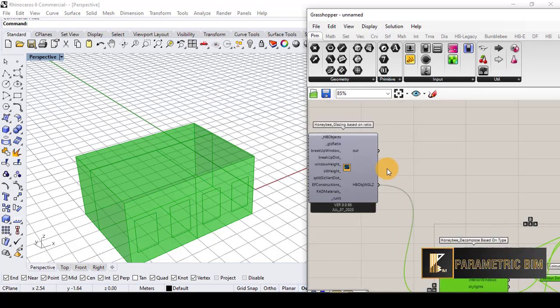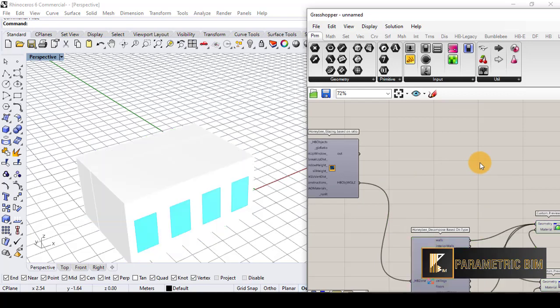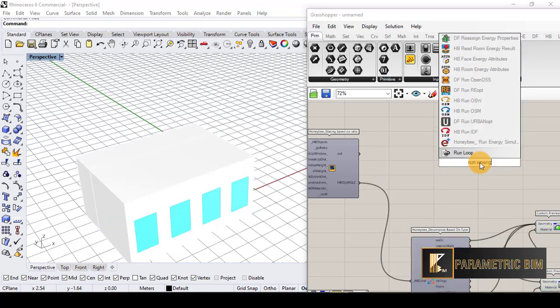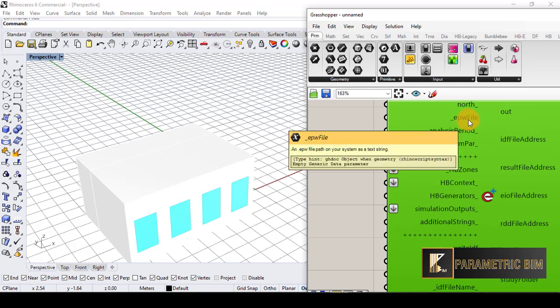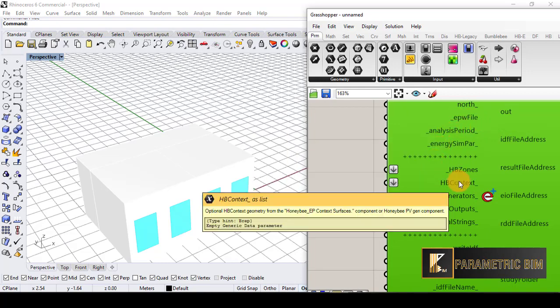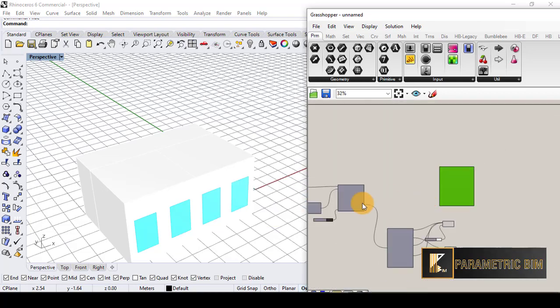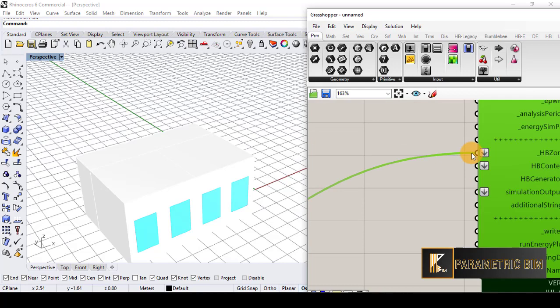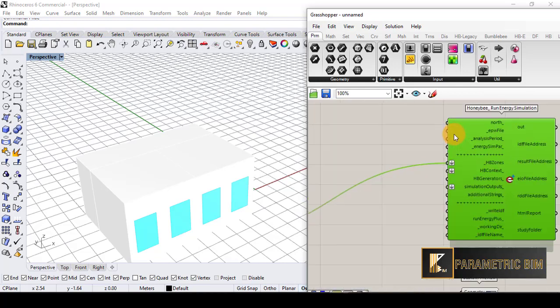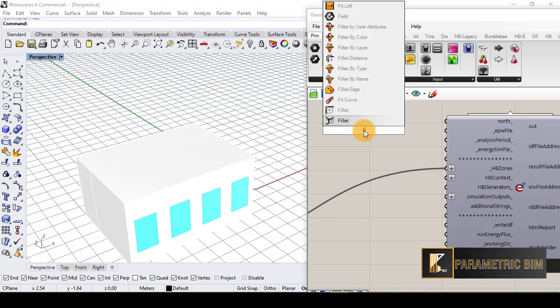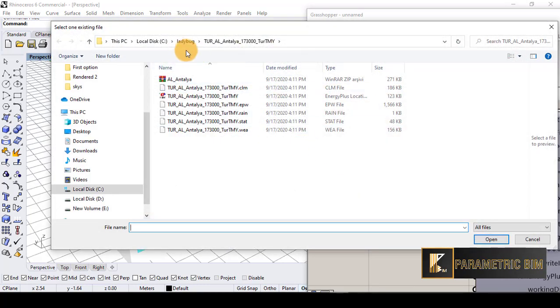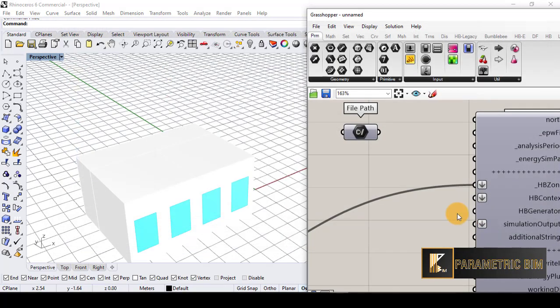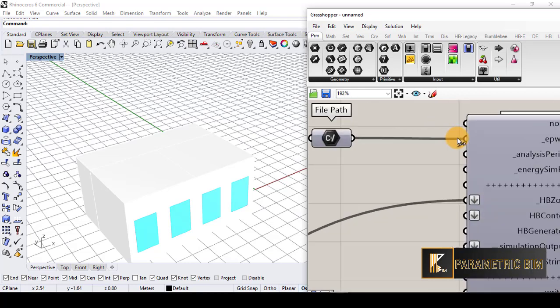Now we need to bring the 'Run EnergyPlus Simulation' component. Looking at what we need: we need an EPW file and we need the Honeybee zones. I will connect the Honeybee zones to the energy plus simulation. I need an EPW file, so I'll double-click, add a file path, right-click and set an existing file — I'll use an EPW file for Antalya city and connect it to the EPW file input.